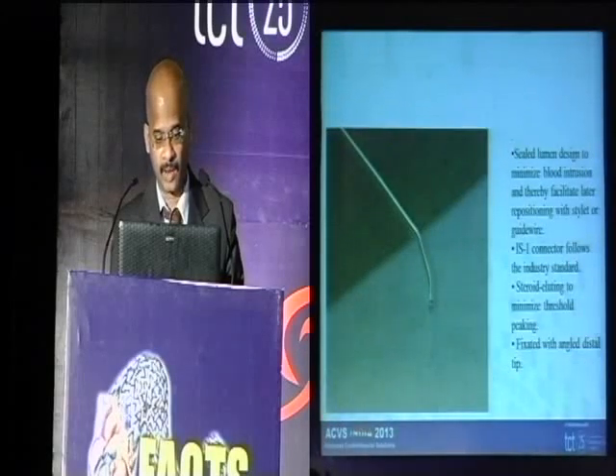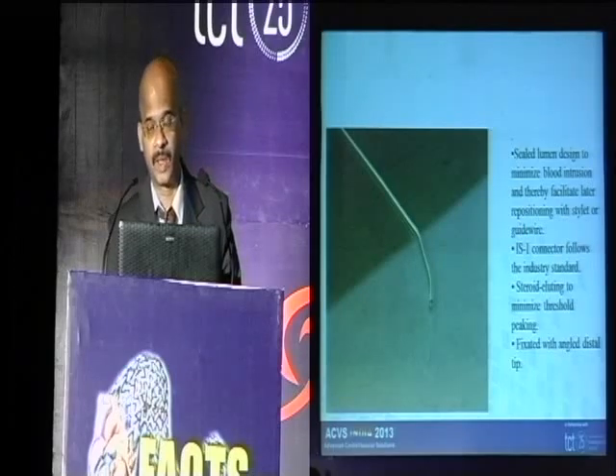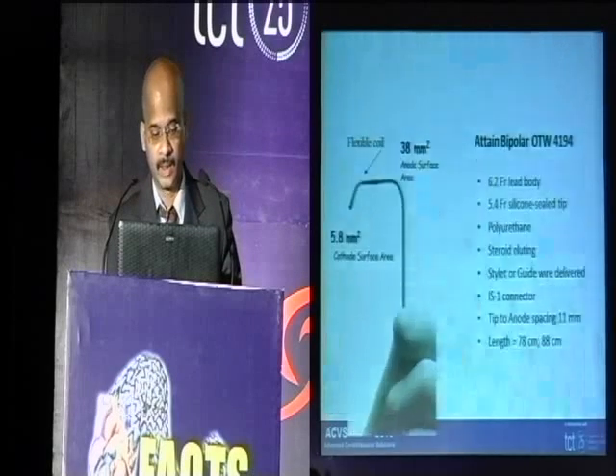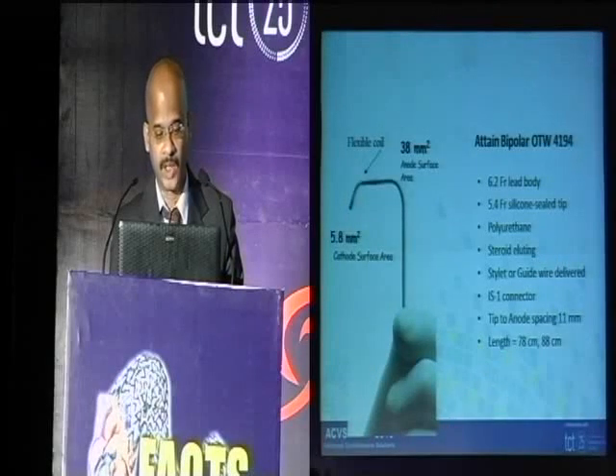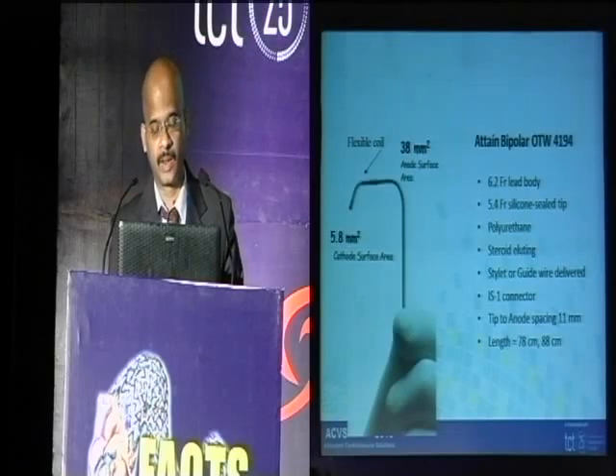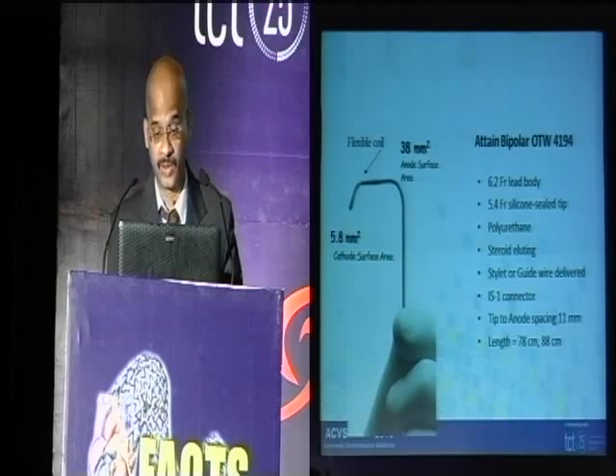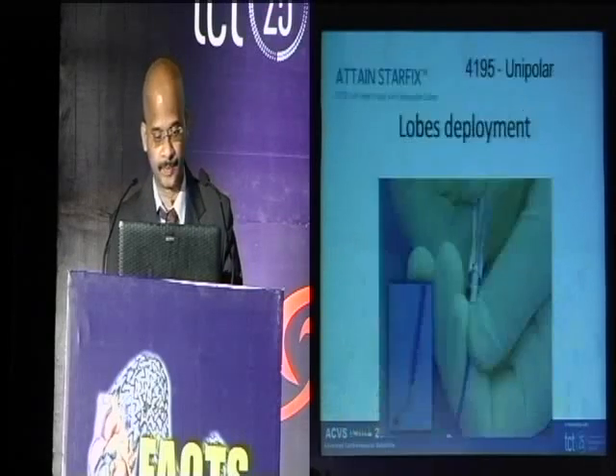And this is the picture of how the lead follows the guide wire, and also the lead shape actually becomes a little bit straighter. And this is the lead without putting any wire through. Although it looks to have two curves, as soon as you put the lead over the guide wire, it tends to straighten up and you can negotiate most of the branches without any difficulties.